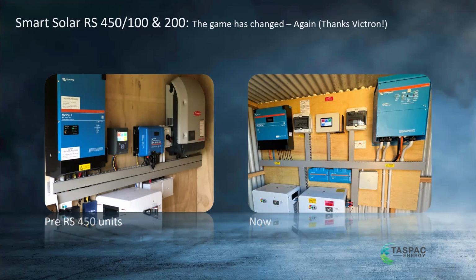The Fronius would normally take the bulk of the panels, and the DC charger was used for what we call black start. You definitely need some DC in a system so that if the power goes off, or the battery goes really flat and the inverter turns off, the next day that DC coupled solar is responsible for charging the battery back up, even though the system is dead.